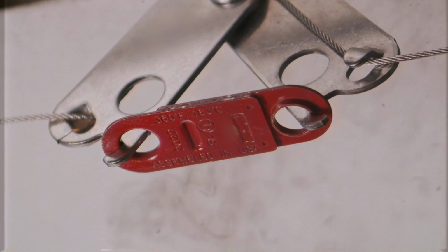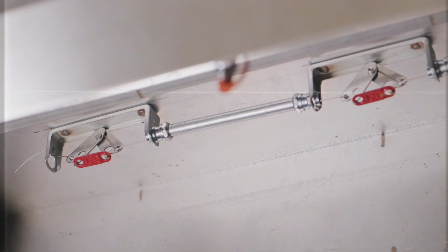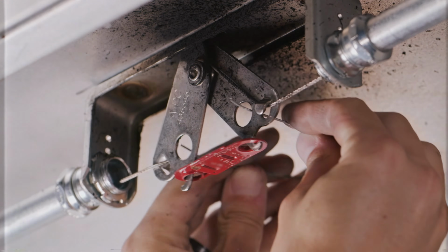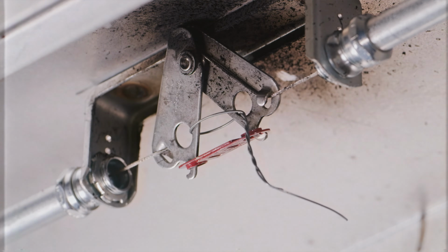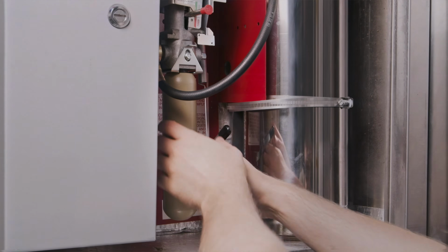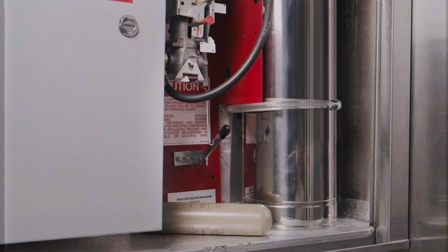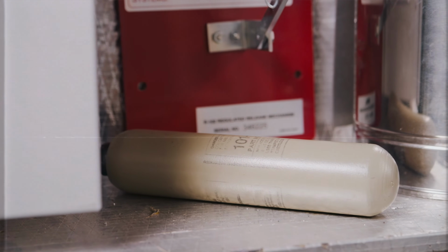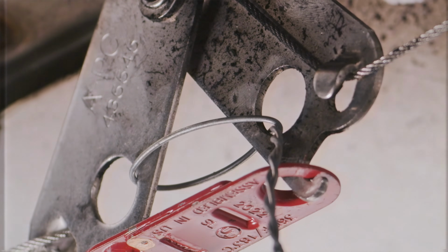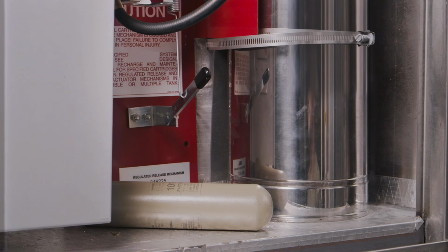Unlike traditional fusible link systems, there's all kinds of things that go on with regards to that. So with fusible links, the guy's going out to do a service on that. They may take a piece of wire and connect the linkage in the link system, so accidentally the fusible link doesn't pull apart, or they might remove cartridges that are used to activate the tanks. They can also be removed. Those systems wouldn't be monitored. Potentially you could have a service guy walking away from a job site and he's basically made that fire system inoperable, because if the fusible link snaps but there's a cable tie or some type of wiring, it's not going to relieve that pressure, which is then going to activate the system. And or if that cartridge is missing, then you don't have the nitrogen you need to fire that system.